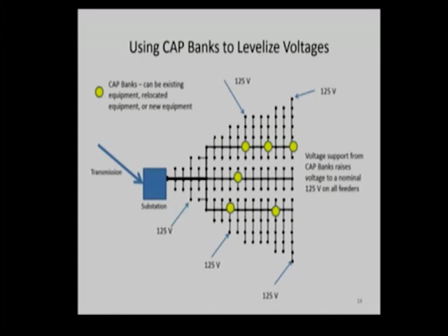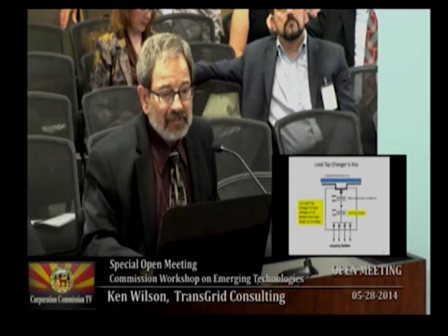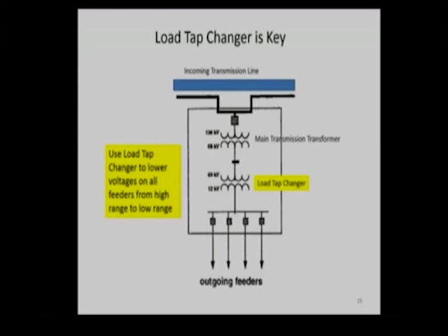And you're thinking, well, we talked about lowering the voltage, why are we raising them? But what we need to do first is to make them level at some voltage, and then we can use that load tap changer to lower the voltage into a lower range. And this is really key, because if you don't levelize the voltages out in the grid, then you can't do a good job at the substation of telling the load tap changer to lower all of the voltages and still be in a safe range for all of the customers.